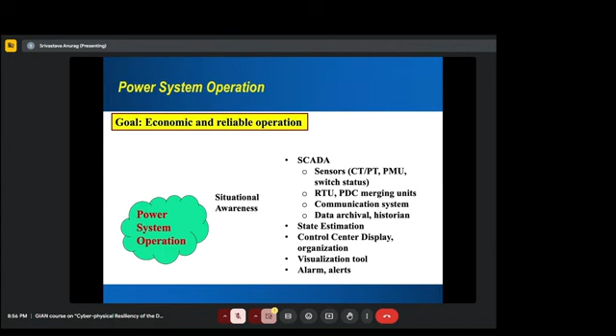Okay. Now, the next part we do, after state estimation, is power flow and other things, and then we display and organize that information. And then we use that to send alarms. An alarm is, okay, this substation has higher voltage than it should be. This line has more power being transferred than it should be, right? So those are alarms and alerts that go to the substation engineer and control room operator, and then from there it goes to the crew so we can fix it.